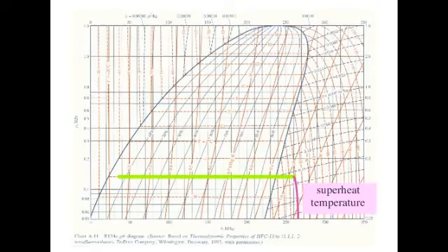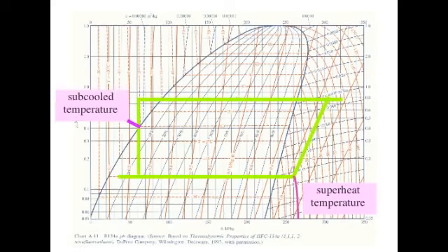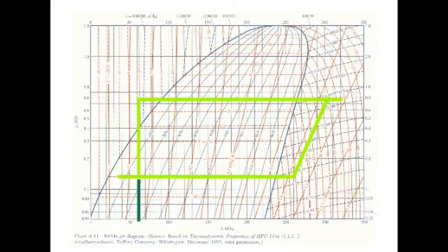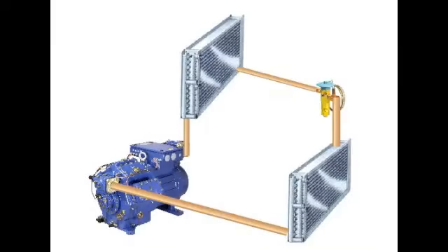We have assumed the vapor leaving the evaporator was saturated, that it's still at the temperature for the phase equilibrium between liquid and gas. Likewise, we assume the liquid refrigerant leaves the condenser at saturated conditions. In fact, it is more common to allow the vapor leaving the evaporator to become superheated by 5 to 20 degrees. This somewhat improves performance and ensures that only vapor enters the compressor. Likewise, the liquid leaving the condenser may be undercooled.